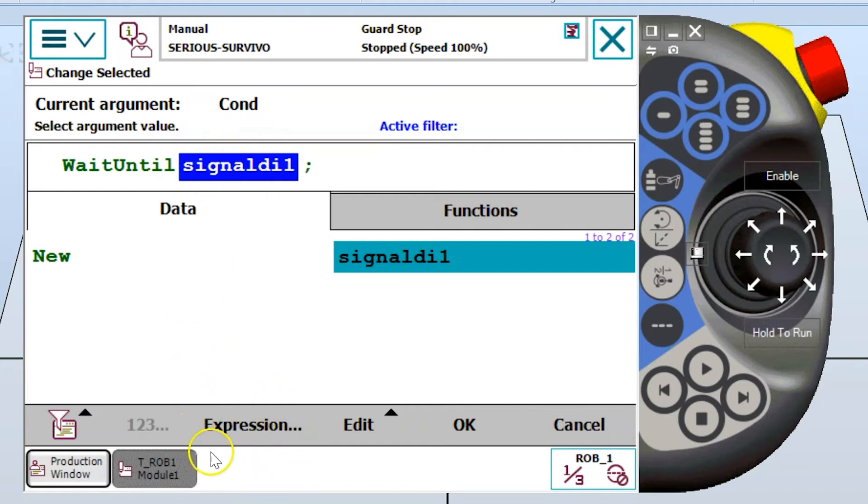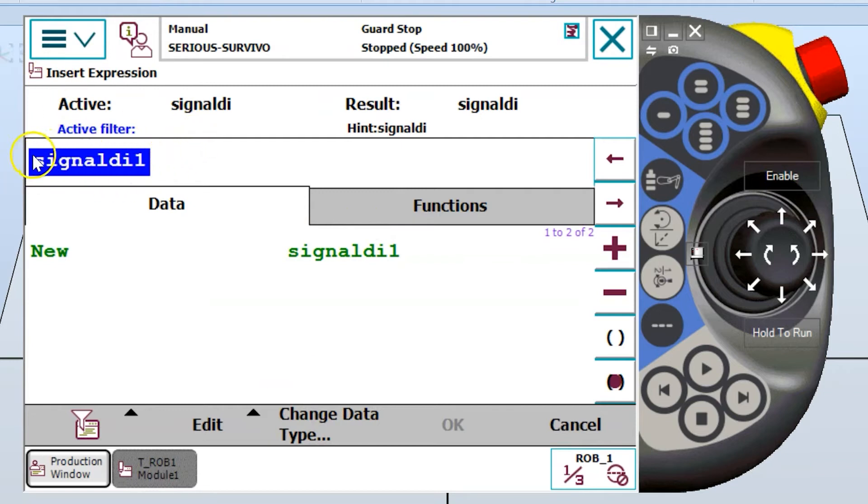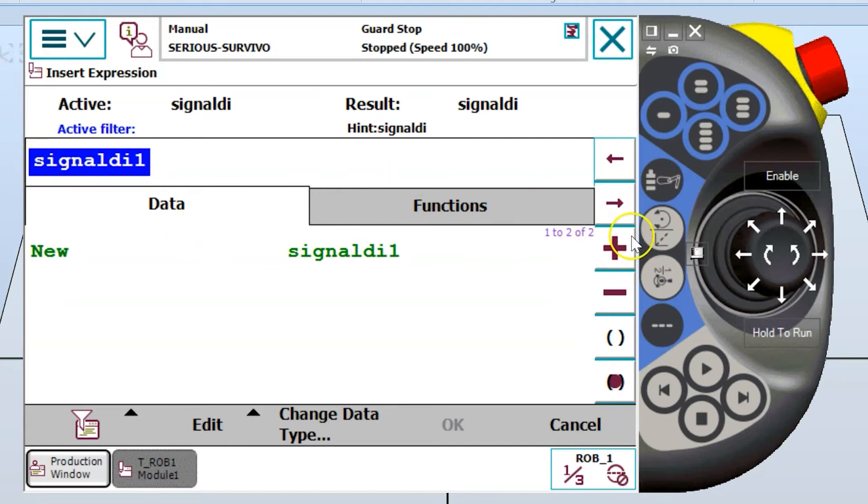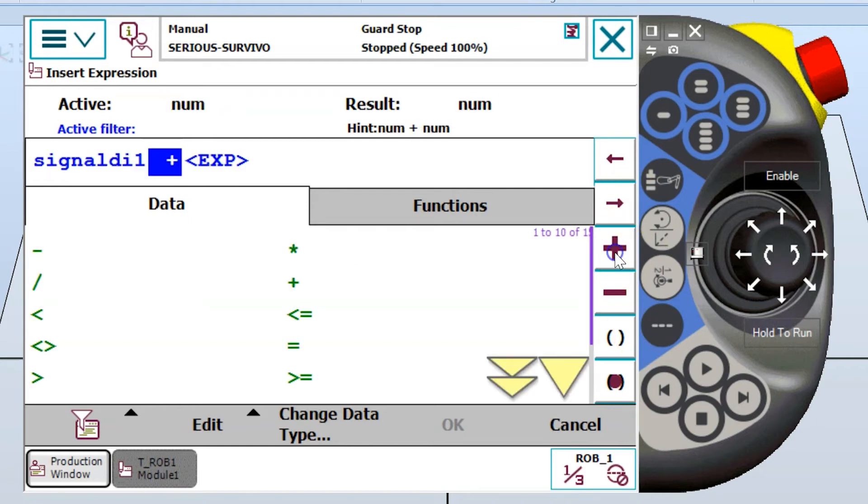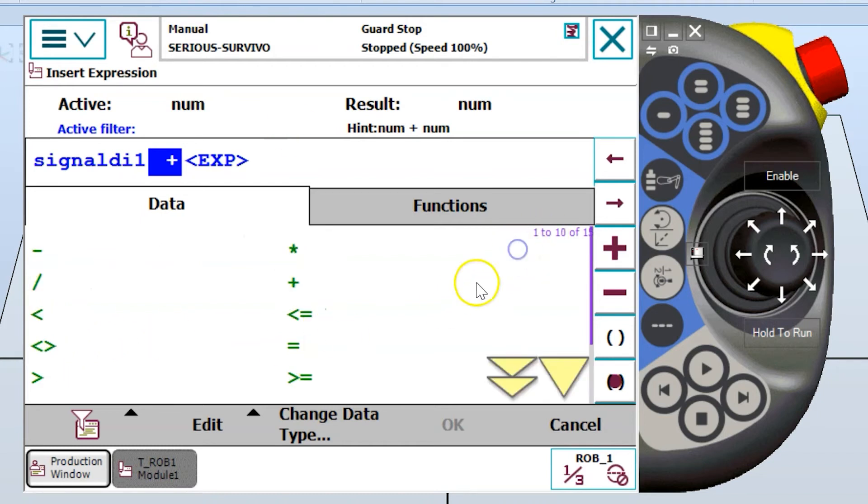And the way I do that is with this expression button at the bottom. I press expression and it looks very similar, except for one thing I see that this is by itself. I don't see the wait until instruction anymore. So if you use your plus sign for your mathematical operators over here, then it's going to bring up these operators. And if you scroll down, you can see some Boolean logic there. I'm going to say equals because this is a digital input. So I can wait until it equals one or equals zero.